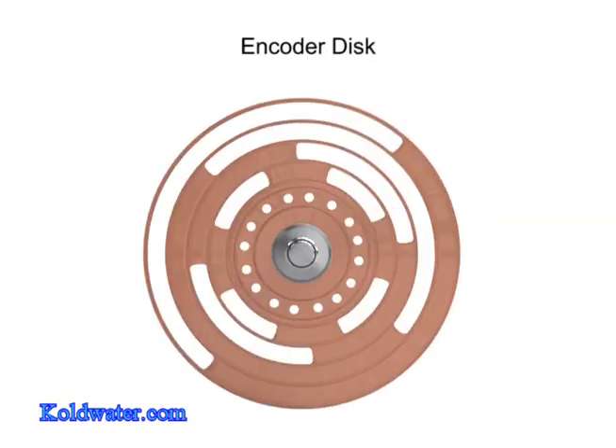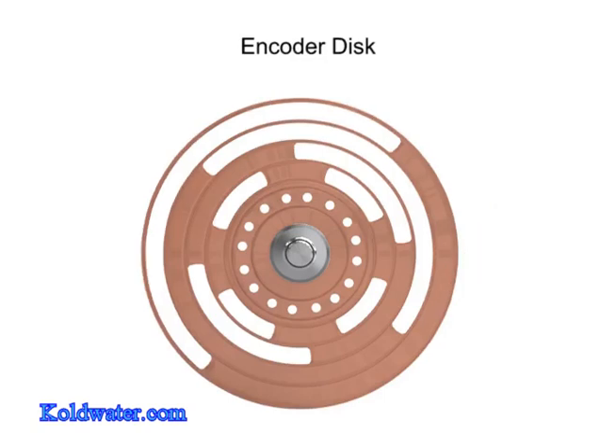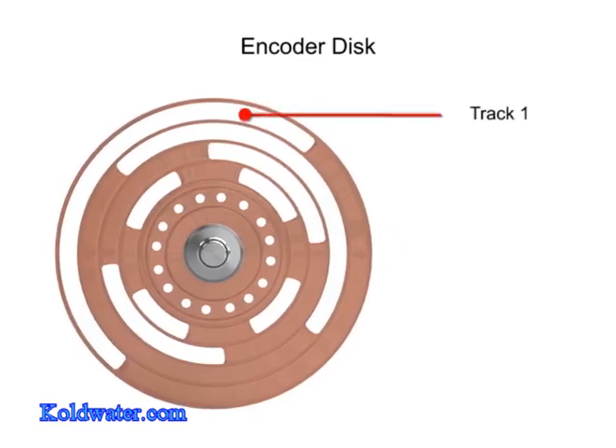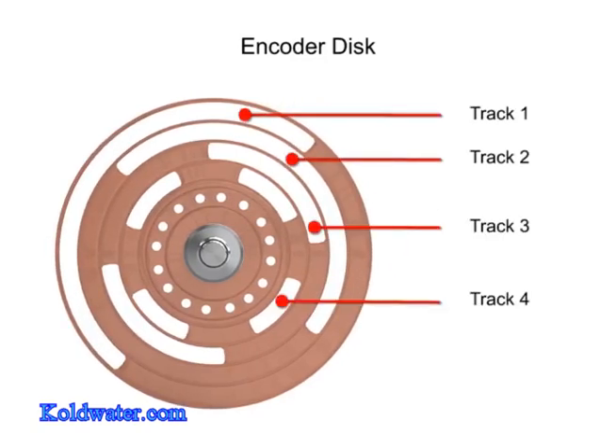The encoder disk consists of a series of opaque and transparent tracks mounted to a rotating shaft. The tracks of the disk are arranged concentrically around the center of the shaft. Photo detectors assigned to each track designate the resolution of the encoder. The higher the number of concentric tracks, the higher the accuracy.